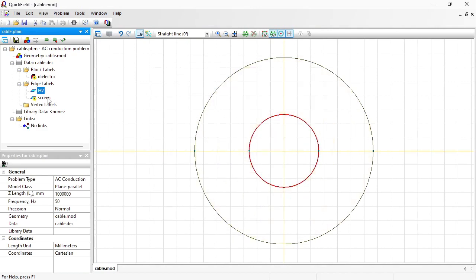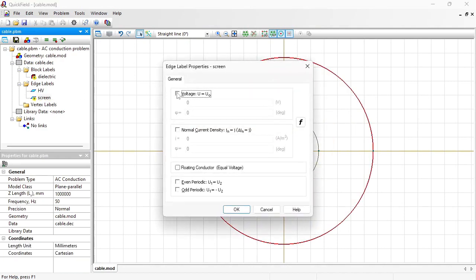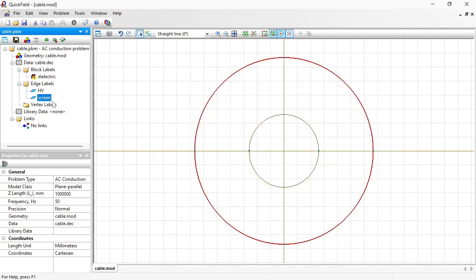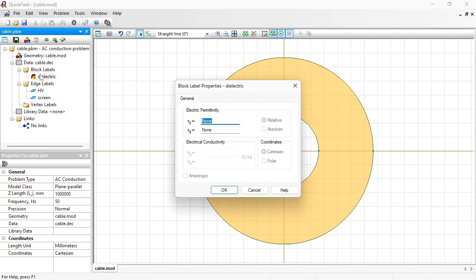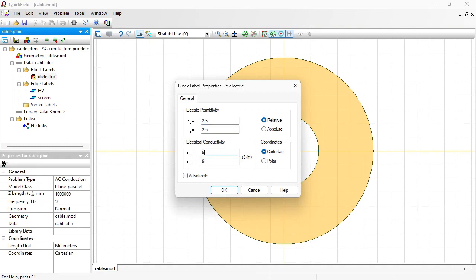The screen is grounded. Zero electric potential. For the dielectric I specify the electric permittivity of 2.5 and the apparent value of electrical conductivity that will allow me to calculate the losses in the dielectric. This is 6.95 pico siemens per meter. Pico means times 10 to the power of minus 12. Okay.